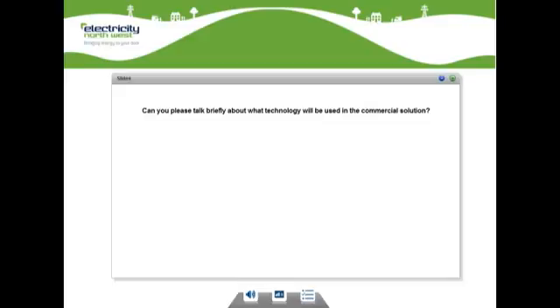What technology will be used on site is very much a learning experience for ourselves, because we need to try and understand what is already there, and we expect every customer will be unique in their own way. Certainly as part of the trial for combined heat and power units, one thing we're going to try and exploit is looking at existing protection on those units and whether a trip signal can be inserted into the existing protection for that unit on site. If there's no existing protection, then perhaps we'll need to do some additional installation work.